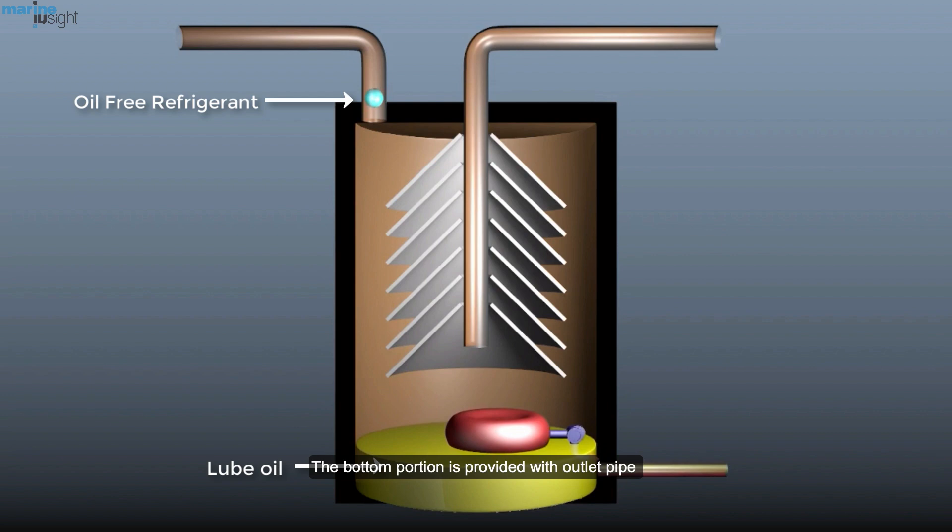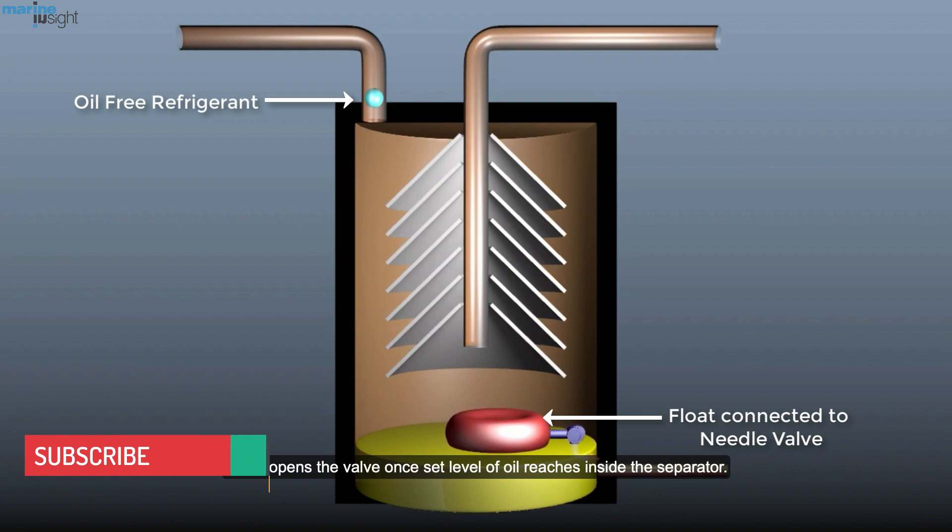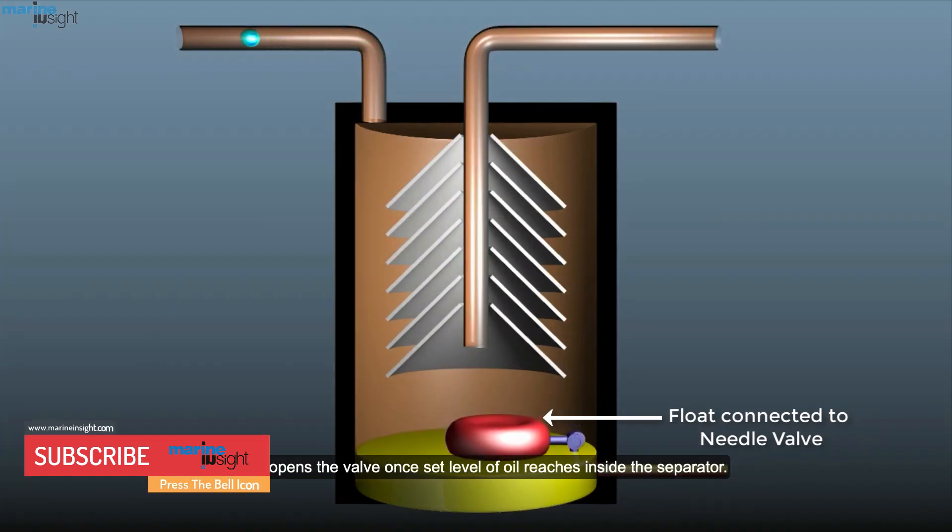The bottom portion is provided with outlet pipe which is connected to the suction of oil compressor crankcase. There is a float operated needle valve arrangement which opens the valve once set level of oil reaches inside the separator.